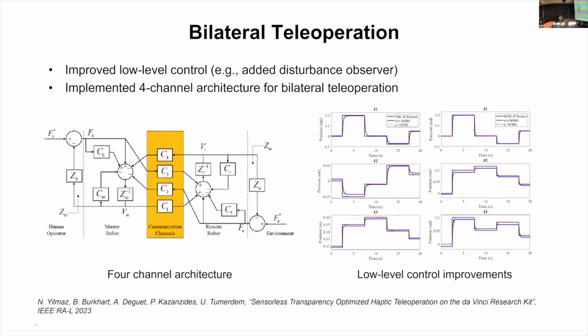But we also wanted to look at doing bilateral teleoperation, which means that, normally in a Da Vinci, it's unilateral. You're moving the input device and it's sending positions to the robot in the body. Bilateral means that forces from the robot measured by the robot are coming back and you get haptic feedback on the input device. And so here we did find that even having decent force estimates, the haptics was just awful when we first tried it. And so we really had to dig into the low-level control, make some improvements in low-level control, and implement this 4-channel architecture, which is kind of the standard for bilateral teleoperation.